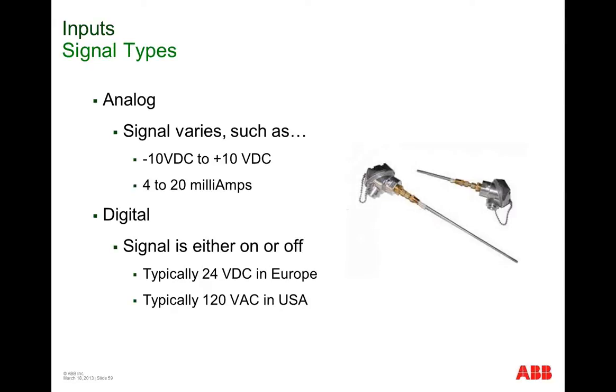Another form of an input would be what we call analog signals or digital signals. In this case, these are temperature probes. An analog signal varies between plus and minus 10 volts DC. It will vary in proportion to the temperature that it's measuring, so it can measure a range of a particular parameter. A digital signal is either on or off, like a limit switch tripping or a push button being switched off or on. Typically, digital signals in control systems are 24 volts DC in Europe or 120 volts AC in the United States.